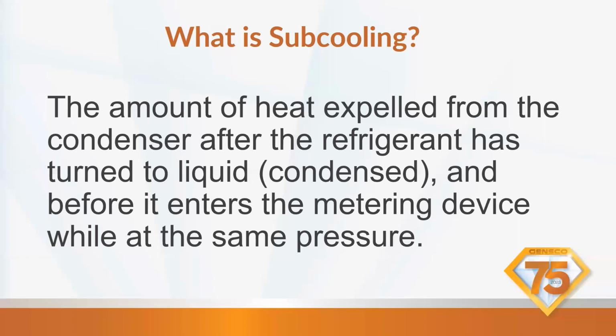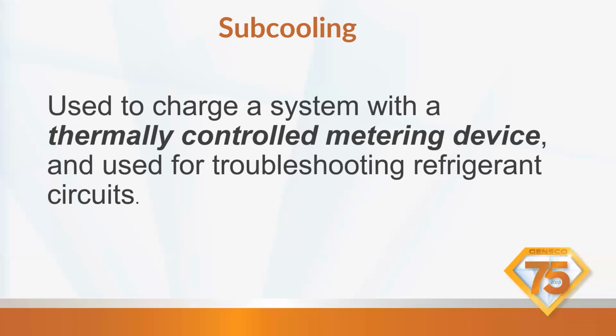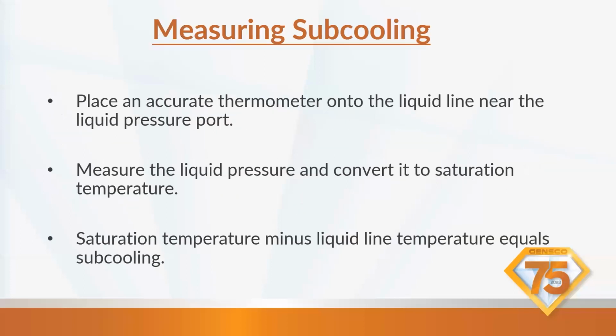What is subcooling? So the subcooling is the opposite of superheat. The amount of heat expelled from the condenser after refrigerant has turned to liquid. So it's entering vapor and it's condensing into a liquid form, and before it enters the metering device. So we want liquid going to your metering device. We want the refrigerant in liquid form at the same pressure. So it's going to be changing state of refrigerant from vapor to liquid while at the same pressure. So the point below that saturation temperature is subcooling. It's used to charge a system with a thermally controlled metering device and used for troubleshooting refrigerant circuits. When you're measuring subcooling, you're going to place an accurate thermometer onto the liquid line near the liquid pressure port. Measure the liquid pressure and convert it to saturation temperature. Saturation temperature minus the liquid line temperature equals subcooling.